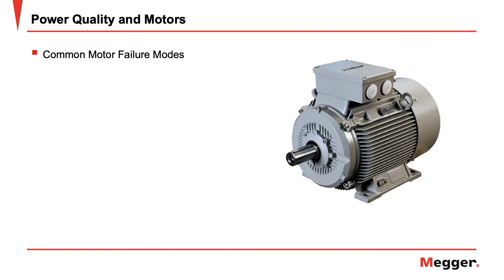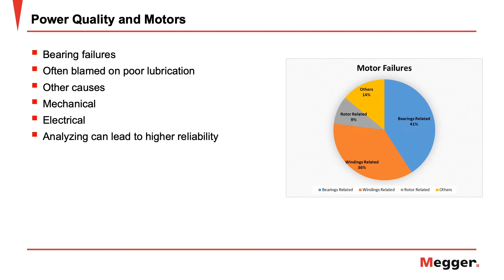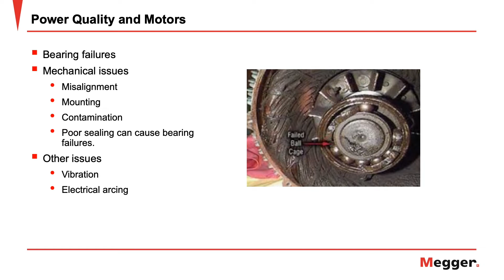However, there are other causes of bearing failures, and these can be mechanical issues or their root cause can be due to power quality phenomena. Mechanical issues such as misalignment, faulty motor mounting, contamination, or poor sealing can cause bearing failures. Other issues that can lead to premature bearing failures include vibration, as well as electric current passing through the bearing, creating arcing.